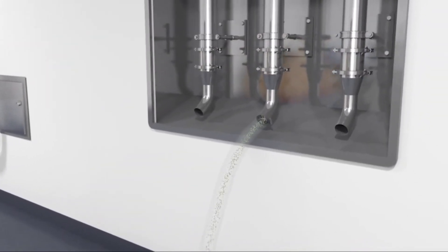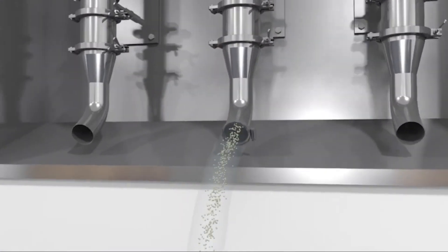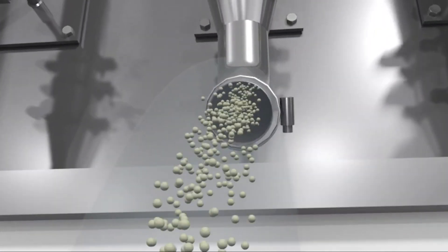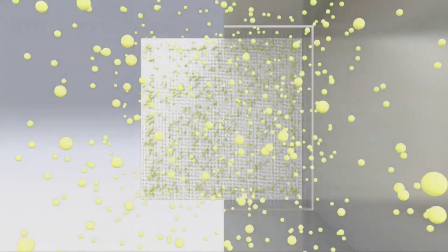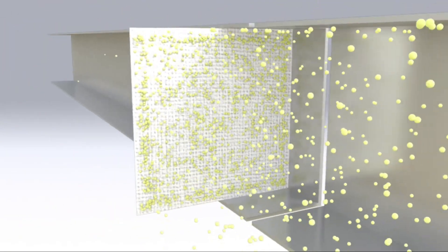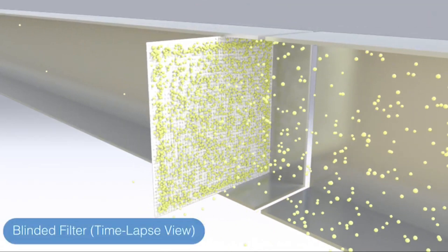Material passes through pipework to the central extraction system or vacuum cleaner, which can create a dangerous mix of powders in the system and will regularly cause downstream filters to block. As filters blind, they negatively impact airflow and pressure drop, and can be dangerous, time-consuming, and expensive to replace.